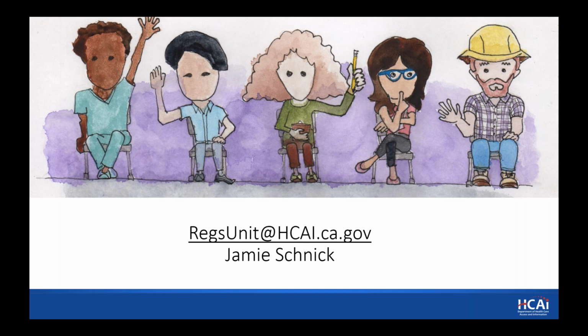So I don't know, this is reading the code, so I don't understand if there is a specific continuation. Sorry, because the person brought the question in 2 parts. This is not a code change, but we understand that there is an HCAI policy change, as there are several hospitals which have equipment branch receptacles rather than normal or optional standby receptacles at the patient bed location. We understand this is no longer approvable and it does not meet the model code. Can you confirm?